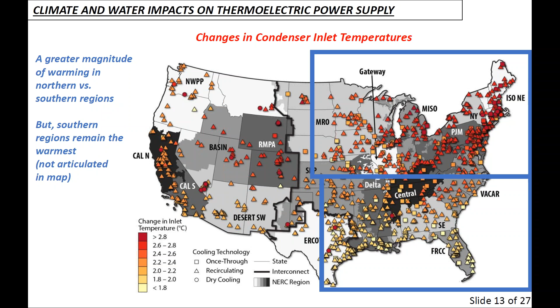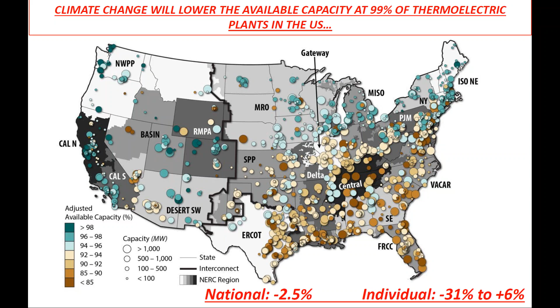We applied those temperature changes in condenser inlet temperatures onto the infrastructure, and found that at nearly all power plants—99% of thermoelectric plants in the US—there are losses in available capacity. At the national level, this equals about a 2.5% drop in available capacity. But there's a huge range in individual impact, from about negative 30% loss in available capacity at some power plants, while a couple actually see an increase. Again, most impacts are in the southeast, and they move northwards because of the increasing condenser inlet temperature magnitude impact on the northern regions. If you hit next.